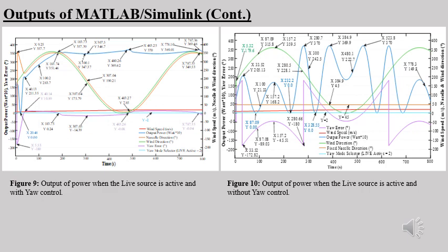There are brief moments when the wind direction accidentally lines up with the fixed nacelle. At 33 seconds, the power reaches about 2.05 kilowatts, and at 157 seconds, it rises to around 1.68 kilowatts. The highest peak of 3.7 kilowatts occurs at 280 seconds when the wind direction is almost the perfect opposite of the nacelle position. Similar short-lived peaks appeared at 383 seconds and 523 seconds, but they do not last.